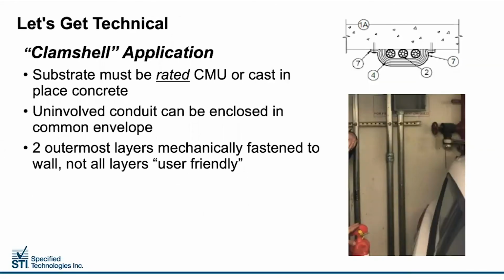So this illustration demonstrates the versatility of EWrap in the retrofit market. The clamshell is a popular installation method due to its space efficiency. Standoffs of 1.5 inches and sometimes less are seen along a cast-in-place concrete wall. This method, when properly installed, will provide a 2-hour rating, where traditional means of shaft enclosure may not be possible. For this system to work properly, the substrate must be rated cast-in-place concrete or CMU.